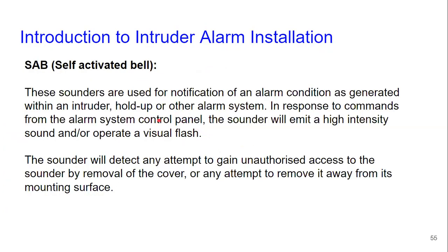SAB stands for self-activated bell. These sounders are used for notification of an alarm condition generated within an intruder alarm, hold-up, or other alarm system in response to a command from the alarm system control panel. Key features: SAB bells come with batteries and are powered by both mains and battery. The mains power from the panel is the primary source; the battery is secondary/backup. The bell will self-activate if either power source fails.